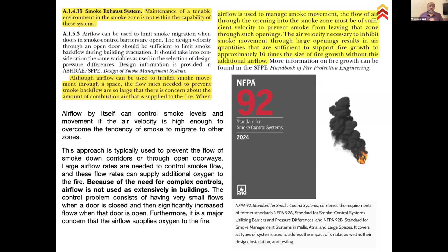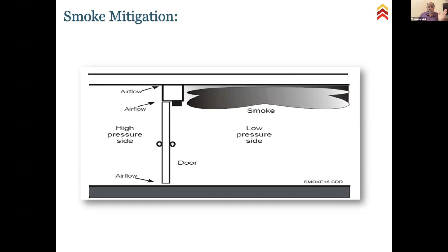This is what it is: you create an airflow, a high pressure side and a low pressure side. What is the high pressure side in this case? The staircase, my dear friends. What is the low pressure side? The zone we call, in our language, the incident zone or fire zone, where the fire has occurred. So you have created an airflow pattern to keep the smoke from entering the spaces used as exits. This is the classical scenario of a staircase door kept on.